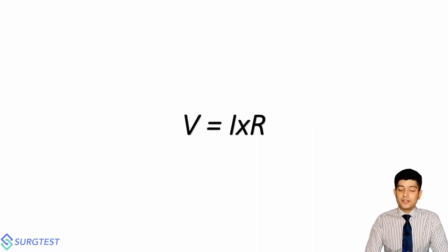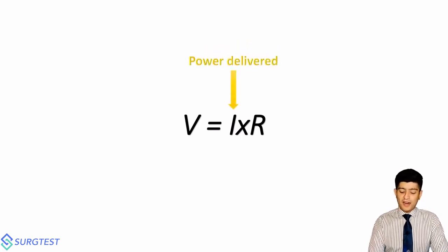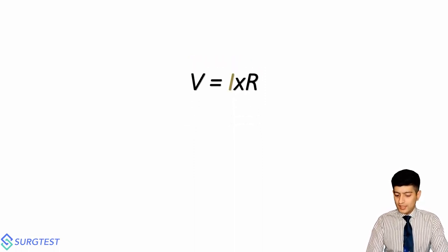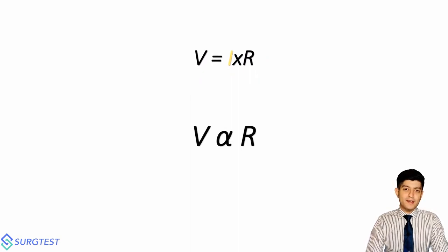Now, voltage is equal to current times resistance. This was a formula that may have been taught in the 7th or 8th standard to all of us. So if I is the current, I'm going to take it as a proxy for the amount of power that is delivered to the tissues. Say we keep I constant throughout, the amount of power that has to be delivered, then voltage is going to be directly proportional to the amount of resistance within the circuit, correct?